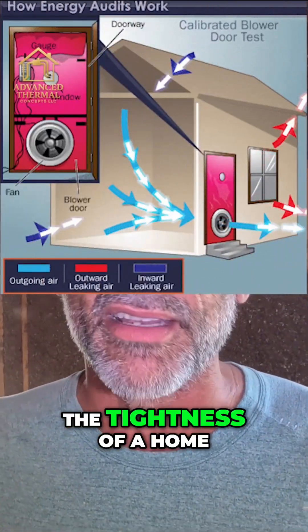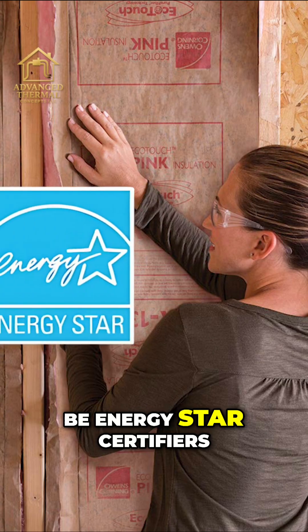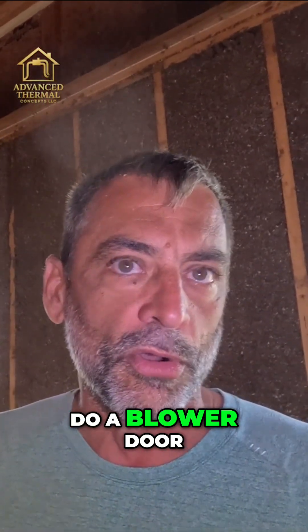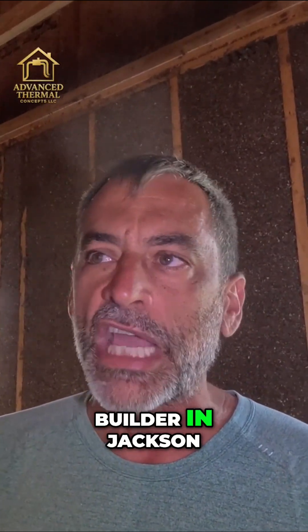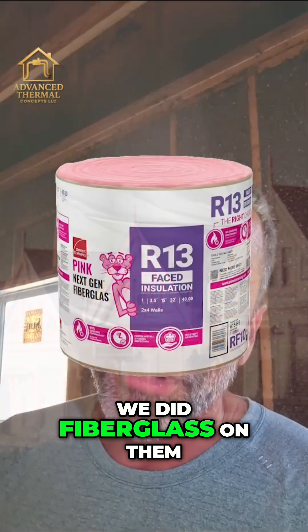Blower door testing is how you test the tightness of a home. We used to do fiberglass all the time and we were energy star certifiers, so to get an energy star home we had to do a blower door test for air tightness. We had a tract builder in Jackson, Tennessee who built the same houses over and over. We did fiberglass on them, we did cellulose on them, and then we did foam on them — so we tested these identical houses that we insulated.